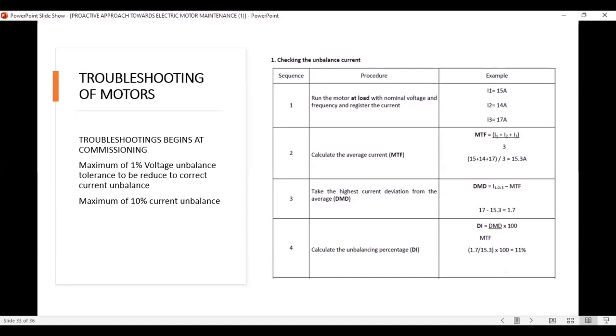For this one, you find the average. The average we got was about 15.3. And you subtract the average from the highest deviation. The highest deviation was 17. So 17 minus 15.3, we got about 1.7. And we find the ratio to the average. And upon that, we got 11%. But physically looking at this, you would think that the imbalance is manageable. So it's always prudent that whenever you commission a motor or you are troubleshooting, you take time to calculate the imbalance to ensure that it's within the acceptable range, or else physically looking will deceive you that the imbalance is tolerable. Next slide, please.